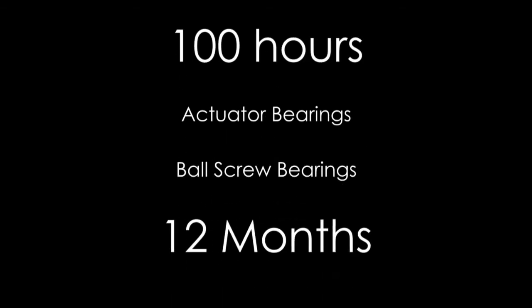Cleaning and greasing the actuator and ball screw bearings should be done every 100 hours or 12 months, whichever comes first.